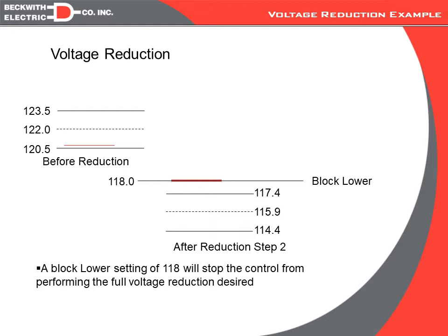So to calculate the block lower setting, one really needs to go into the highest percentage reduction, and then from that figure out what the voltage would be to stay in band, and then you would want your block lower to be set on that particular low edge of the band. So in this case, if I were wanting to actually have this as my lowest reduction, what I'm saying is I'm saying it's okay for the voltage to be 114.4, so I would want my block lower to be set at 114.4 or slightly lower and not the 118, because in this case we will start the reduction coming down, but as soon as we hit 118 we're going to hit the block, and that will stop any additional lowers.